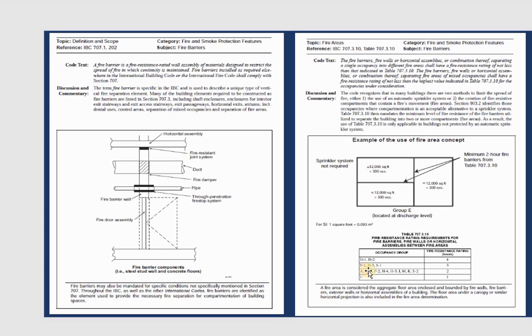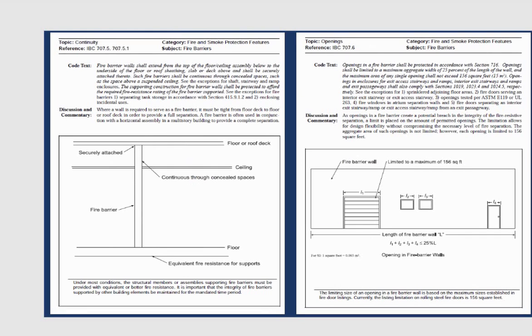If you have F1, S1 (storage), or factory and hazardous occupancy, you need three hours. Looking at Group E — like the earlier example — occupancy groups A, B, E, F2, I, M, R, and S2 require two hours. For Group U, you need one hour. For example, a garage requires one hour between the garage and another room.